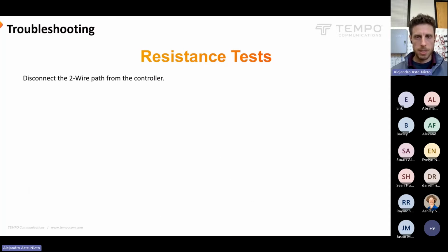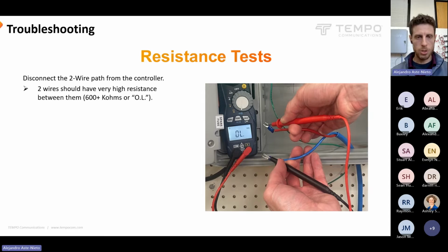Another thing we can do is just take some measurements with resistance from the controller. So we can disconnect the two-wire path and check the resistance between the two wires, and a healthy two-wire path will have very high resistance between the two wires. Above 600 kiloohms, or on the CMA 360B, that's pretty much the upper limit of the resistance test on that unit anyway, so it'll probably say OL on a healthy system. There shouldn't be any real continuity happening between the two wires.